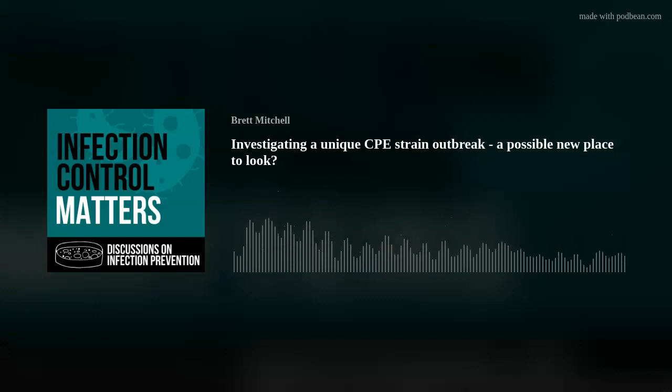If you look at the manufacturer's guidance, it's very clear that you have to store them dry. You actually have to lift them up as well, so you drain the fluid back. The idea is that you're storing them dry. Invariably, what we did find in many of our clinical areas when we looked further afield is that they were not being properly stored, not being maintained as well as they should have been. And there are questions around staff knowledge and training about actually being able to do that.